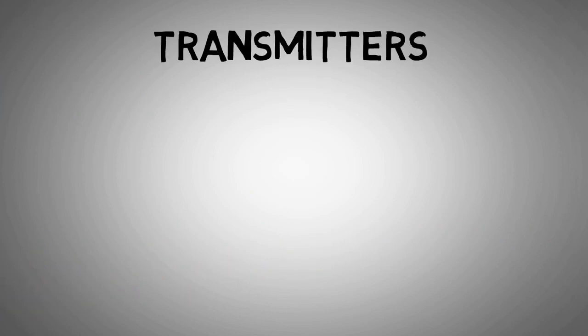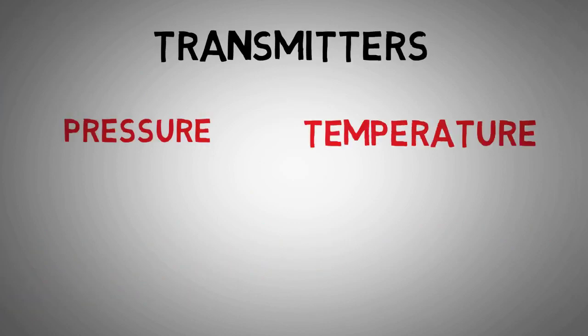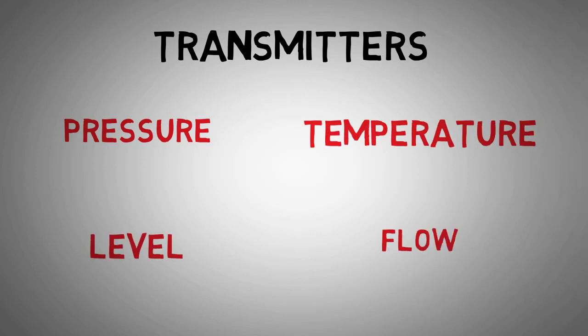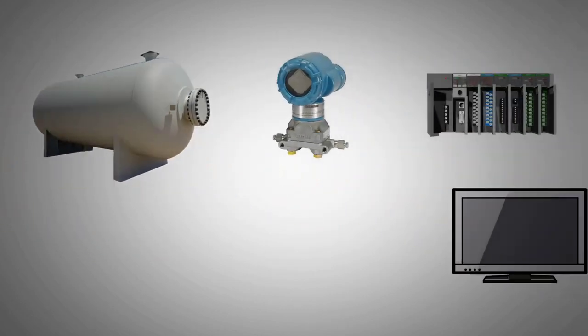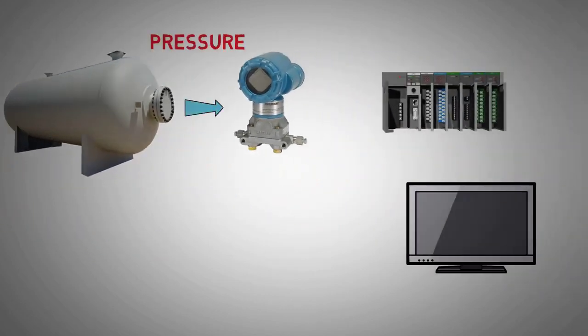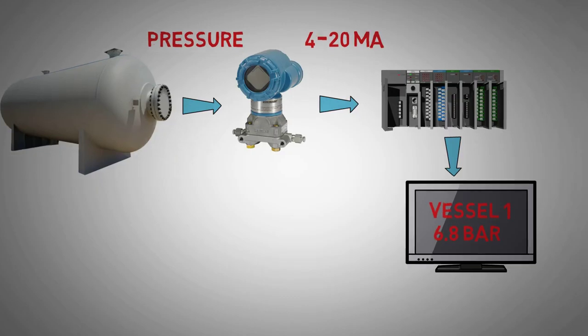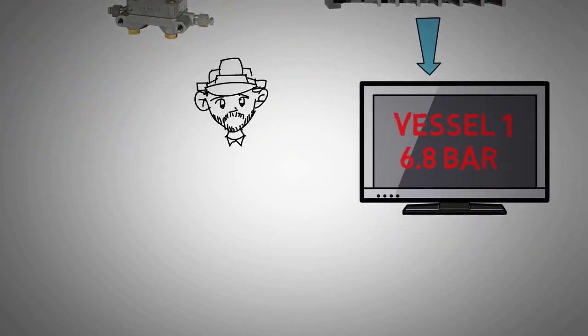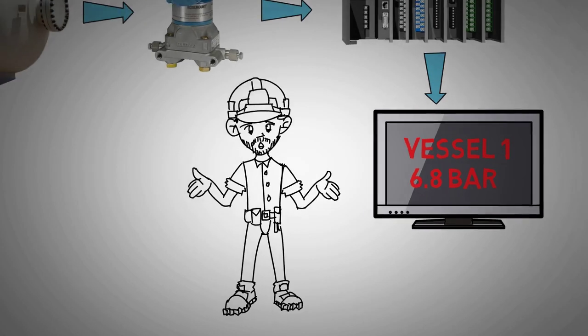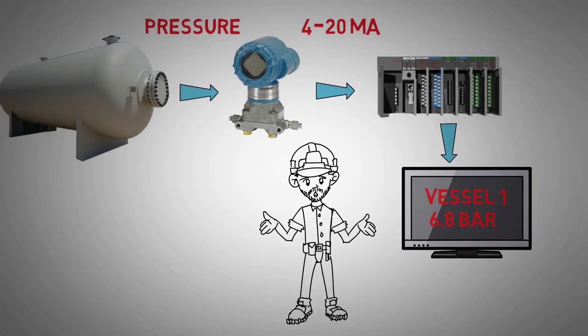As we learnt in the transmitter lesson, instrumentation is measuring the real-life conditions of a plant's process. Let's take an electronic pressure transmitter that is measuring the pressure inside a vessel. The instrument is connected to the site's control system via a 4 to 20 mA current signal. The control system then gives a readout to our control room operator so we can monitor and know the exact state of the plant. But how does the control room operator know that the pressure he is seeing on his screen is the exact pressure that is in the vessel?